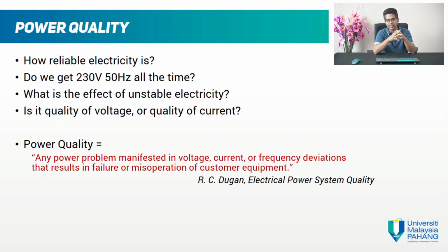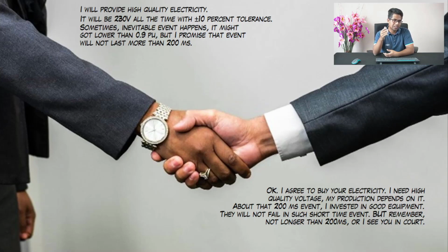One thing about this definition is that whenever there's a power quality event, let's say the voltage drops, but nothing happens on the customer side and production runs as usual, that does not constitute a power quality problem. Whenever there are problems like losses, then it becomes a power quality problem. If not, then it's okay. Why? Because there's an agreement between the utility and the customer.